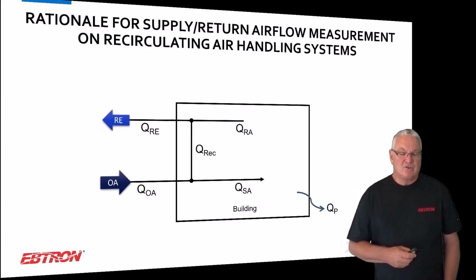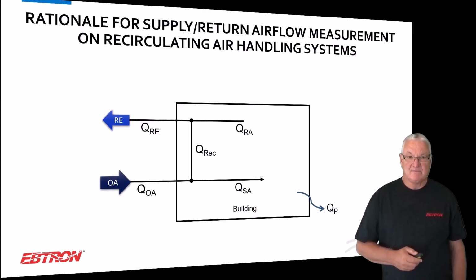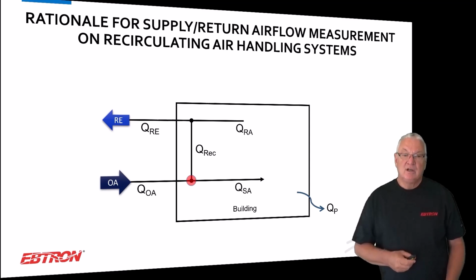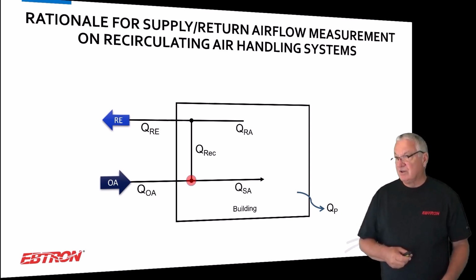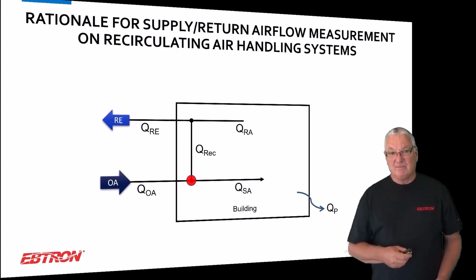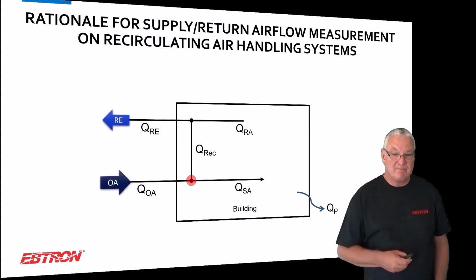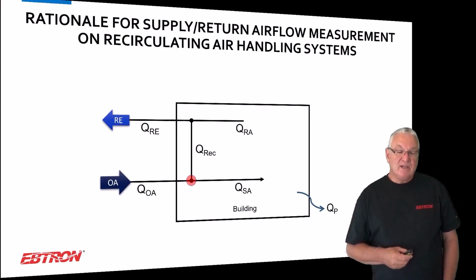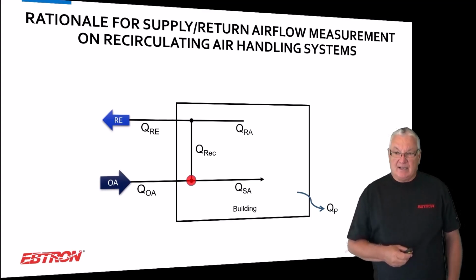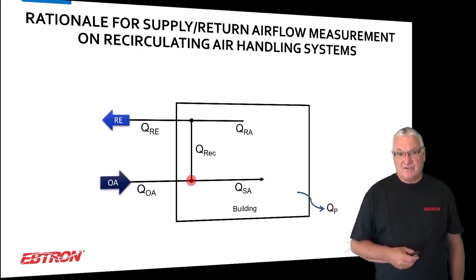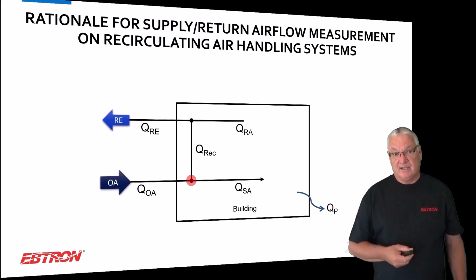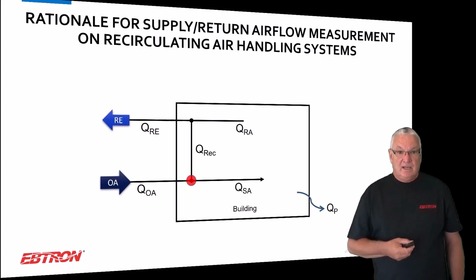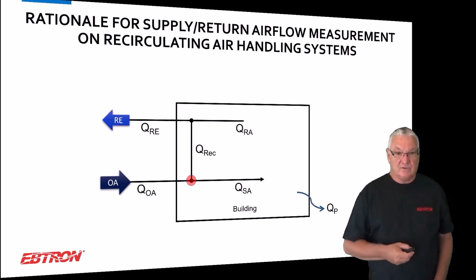And just to make sure that everybody understands on these recirculating air handling systems, the fact of the matter is you do want to know the total ins and the outs, but they're not typically something you can easily measure, okay? Well, the ins you can measure, but outside air is somewhat compromised where you're not going to get 2 or 3% on most outside air intakes. You're going to get closer to 5, maybe 5 to 10, depending if it's a rooftop unit. Relief air is often really difficult to measure accurately. Like I said, I don't believe in using piezo rings for any critical measurements like this. I don't even believe in using flow meters in the relief fans or something like that on systems like this, okay, where we're talking about we need good differential flow control.